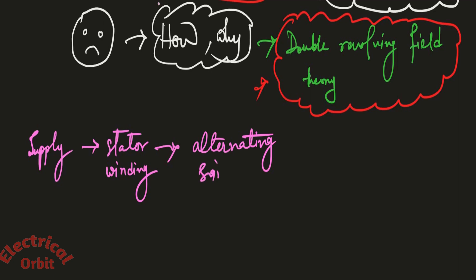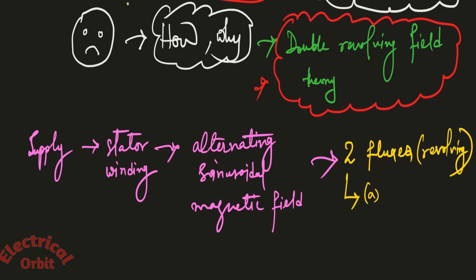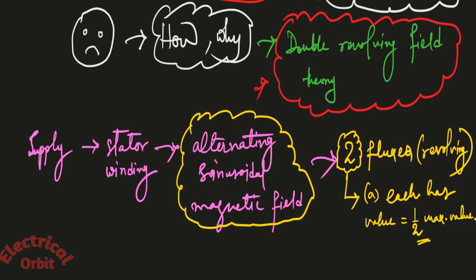Now this particular field can be divided into, or better to say, represented into two fluxes which are of course revolving in nature. An explicit characteristic is that each has a value equal to half of the max value of the flux. That means each of these two fluxes will be exactly half the value of the flux that has been created by the supply to the stator winding of this induction motor. And next is each one is rotating at synchronous speed in opposite direction to each other.